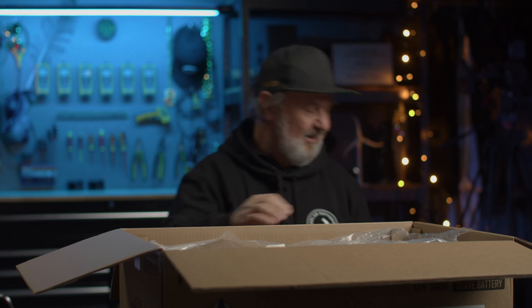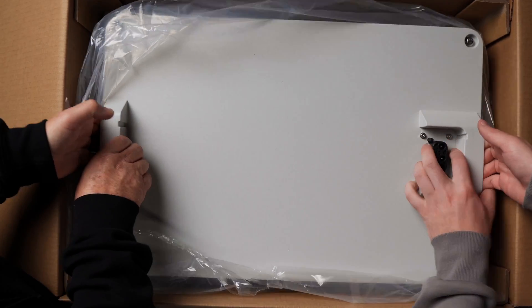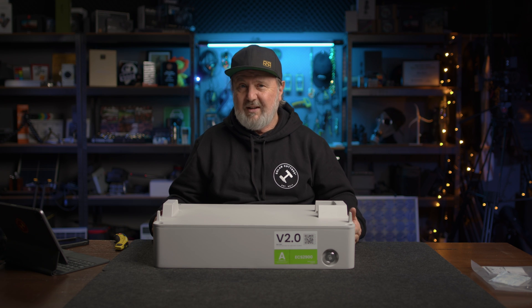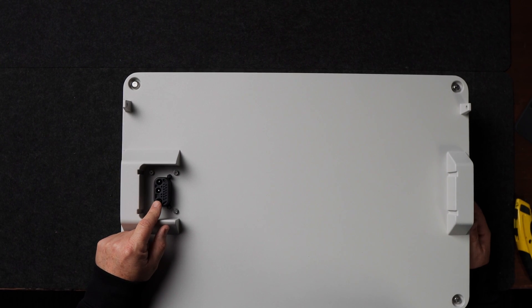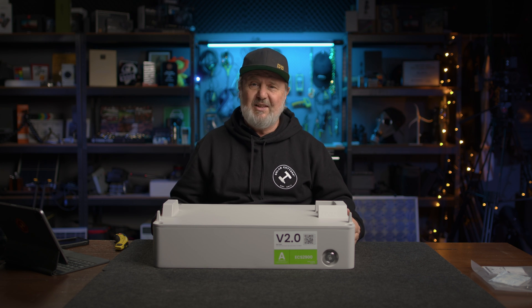Let's get it out of the box — I'll call in my assistant Justin to give us a hand to lift it out. So here we have one component of the Energy Cube. The Energy Cube refers to the full stack of batteries. This connector is both power and data communication between battery modules — the advantage being there are no wires. This system basically just stacks up like Lego and you've got a fully functional battery stack. The top unit is the master, which has the BMS as well, and this one is a slave.